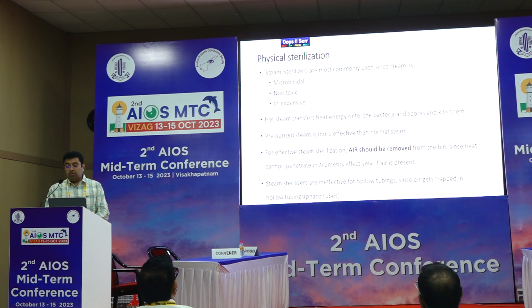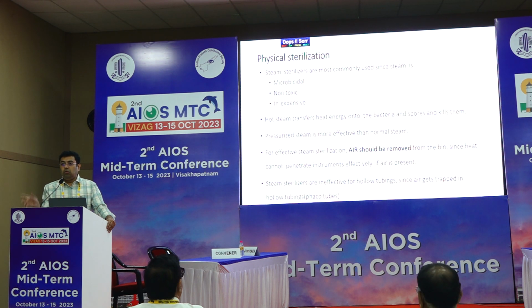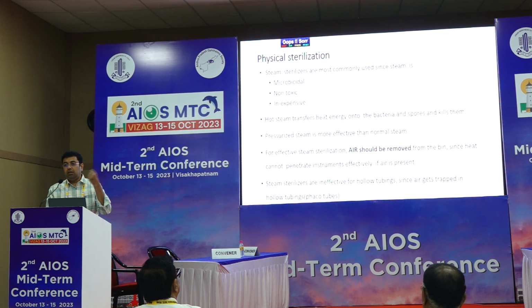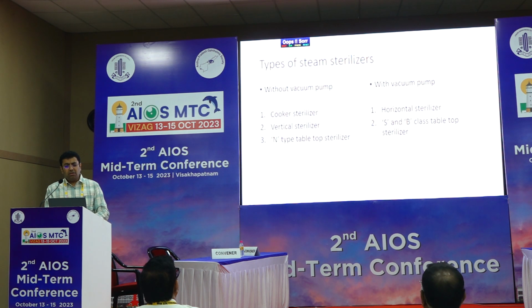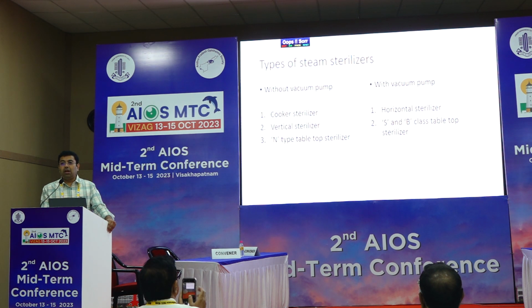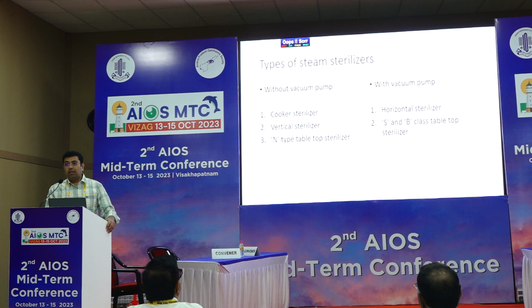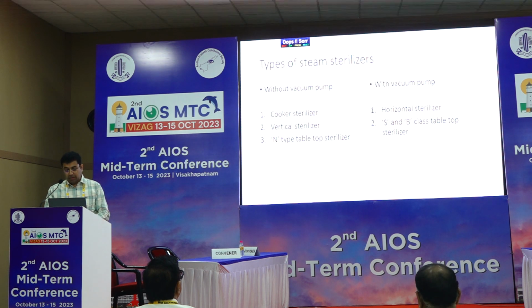Another important thing is that steam sterilizers do not work very well for hollow tubings, since air gets trapped in these hollow tubings. Suppose you take a phaco handpiece or phaco tubings: air will prevent the steam from entering the hollow tubings. You should have an effective mechanism to remove air from all these tubings. With this knowledge, we have two types of steam sterilizers: those with an active vacuum pump which removes the air from the sterilizer, and those without an active vacuum pump.